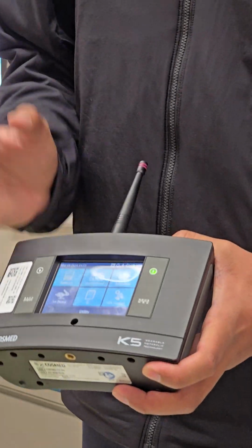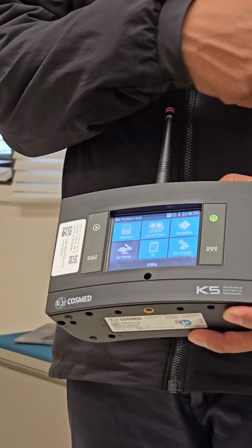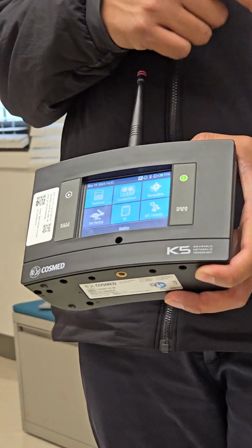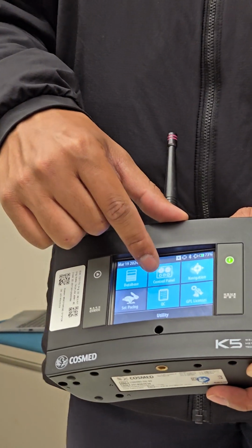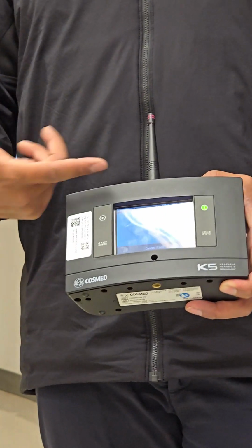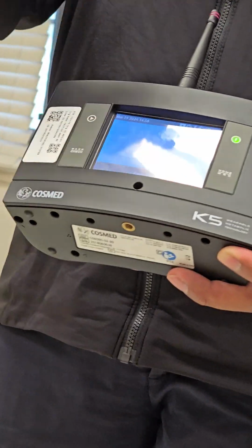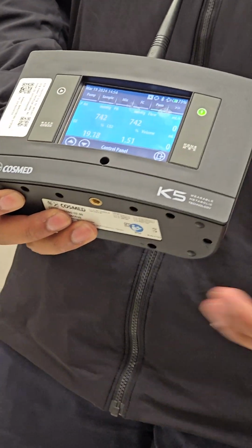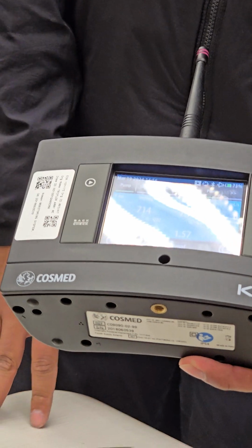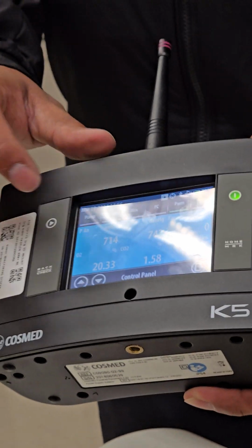Under utility, you do have a database, so if you want to export an entire database, you can do that through there. You have control panel. If we're ever troubleshooting with you, we might ask you to go into control panel, and I'll just show you what that looks like. You guys on your own will probably never go into it, but you can turn off pumps, turn on pumps. It'll show us things that we could diagnose, like what could be going on with the K5. So turn on the pump, turn it off, pump and sample, just different things. Different combinations will tell us what could be wrong with the system. So that's what that's for.